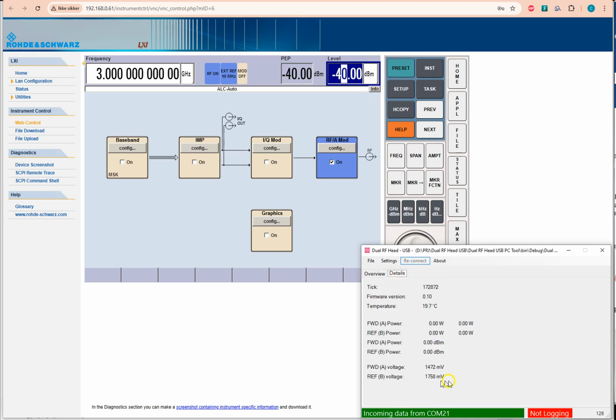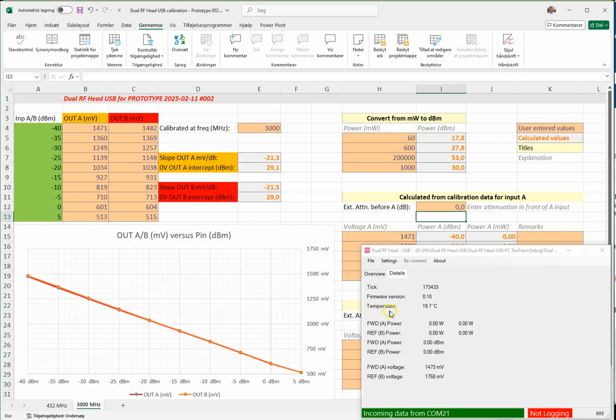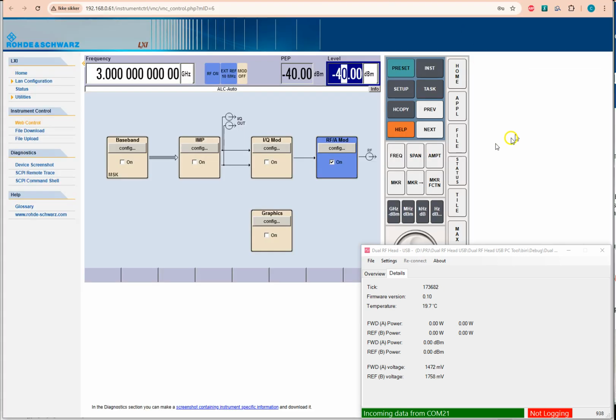We can go to the details tab, and you can see the info. I explained that in another video: firmware version of the software running on the dual RF head, the temperature, internal temperature, and the measured forward reflected power in watts and dBm, and also the raw voltage measured on the dual RF head. One thing I will do here, I will put this stay on top so that it will stay in focus no matter which windows are selected. If I bring up this one, you can see right now on the forward port input A, we have 1472, and the calibration set 1471, so that's close enough. This is due to the fact that we are currently putting minus 40 dBm into the device.